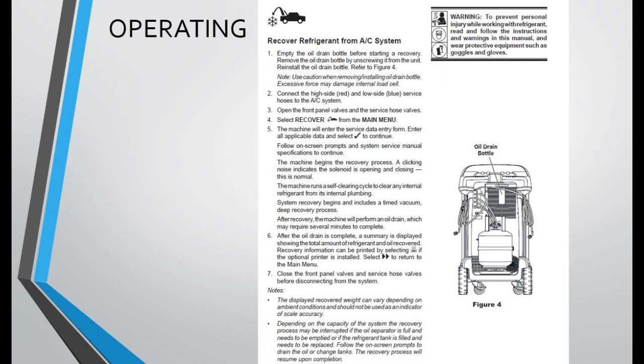Depending on the capacity of the system, the recovery process may be interrupted if the oil separator is full and needs to be emptied, or if the refrigerant tank is filled and needs to be replaced. Follow the on-screen prompts to drain the oil or change tanks. The recovery process will resume upon completion.